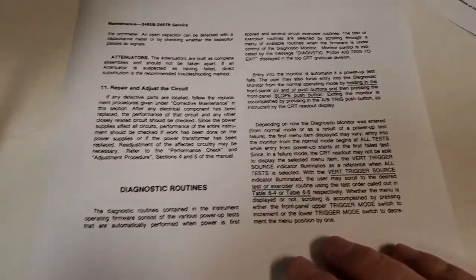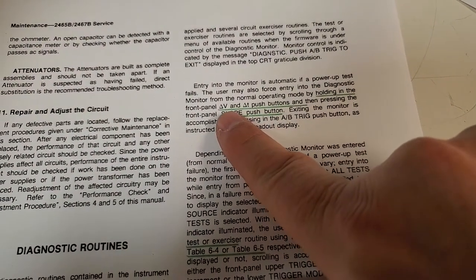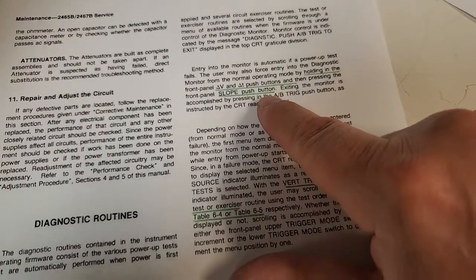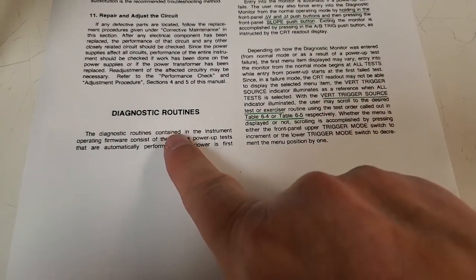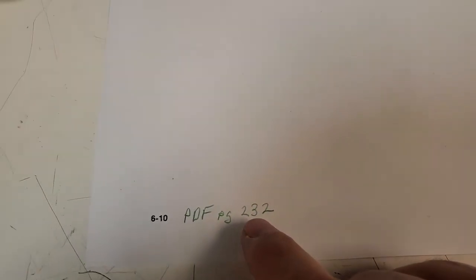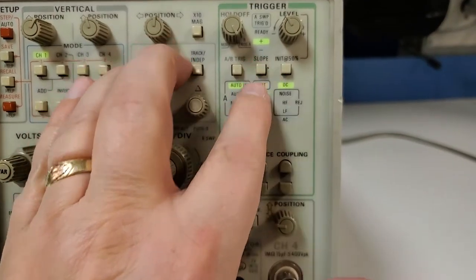You can find that information in the Tektronix service manual. You can go back and access it by pushing the delta V and the delta T and the slope pushbutton at the same time. That's how you get into the diagnostic tests. That's on page 6-10, or in the PDF page 232. So let's go ahead and do that. We're going to hold these two down and push this one right here.